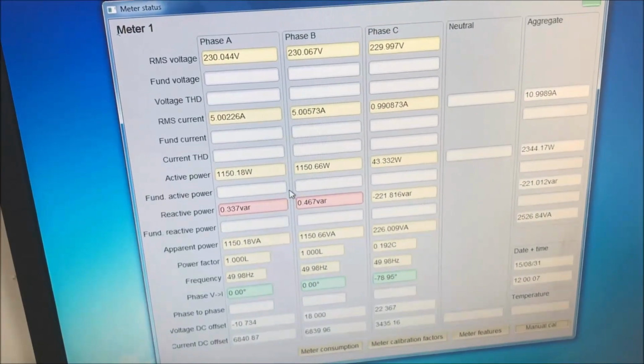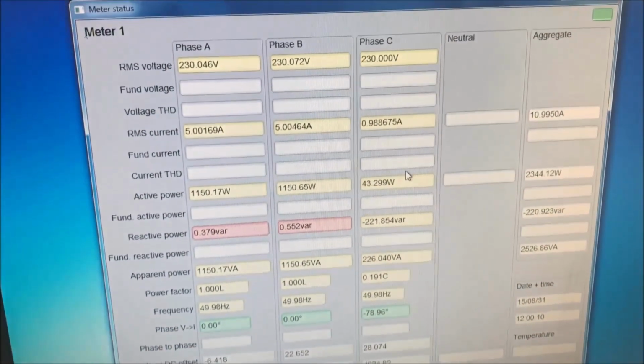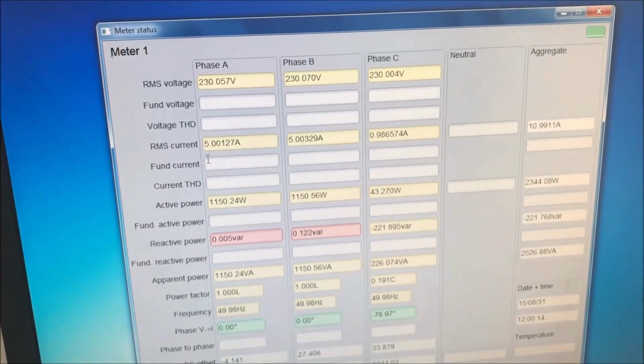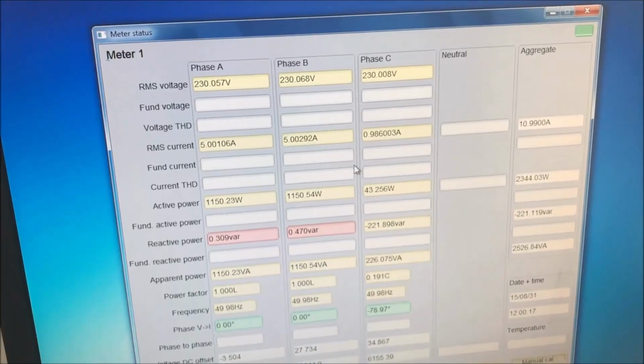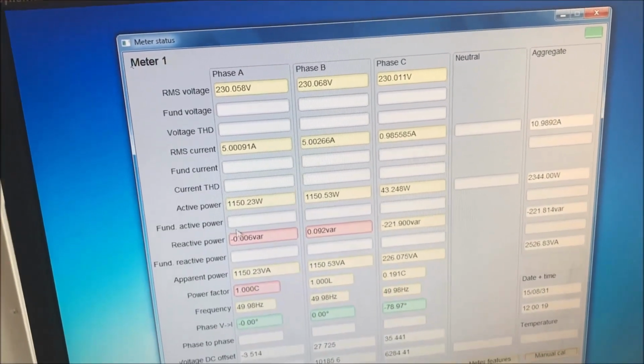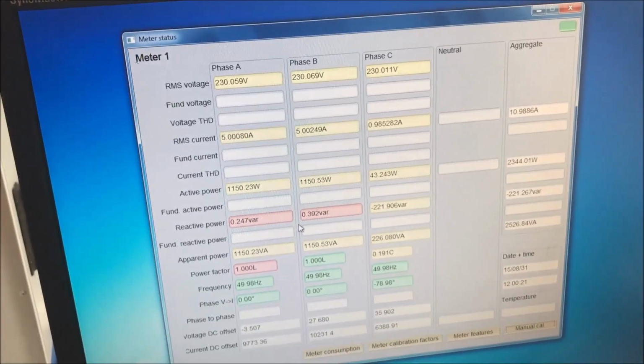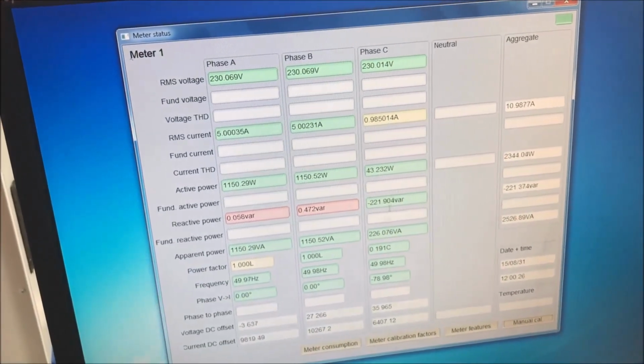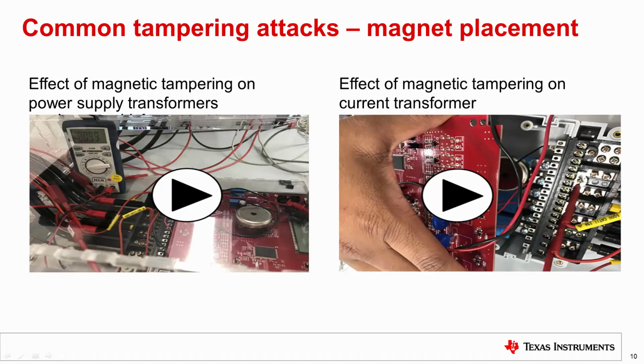Here we see that the active power readings have decreased for phase C from 1150 watts down to 43 watts. As a result, the consumer will be charged much less electricity than what is actually being used. That is all because of the effect of the magnet on the current transformer current sensor. In the video, a physically small size magnet is used to show the effect of magnets on CTs. It should be noted that larger magnets cause a larger drop in readings. A strong enough magnet could even cause a zero current reading from a CT. In addition, multiple CTs could be affected by the same magnet, with the closest CT most affected by the magnet.